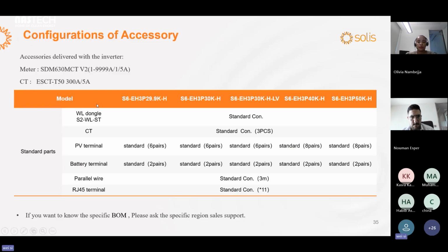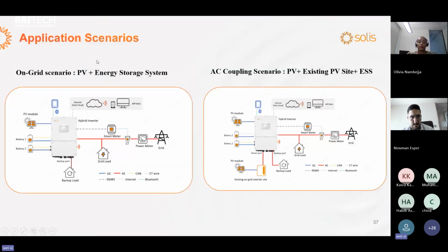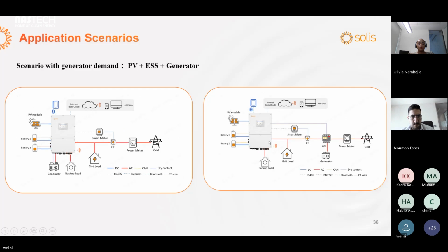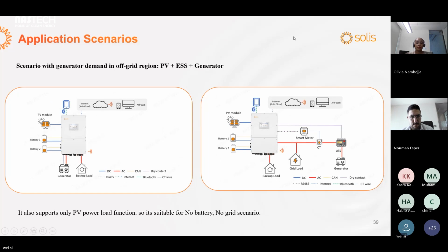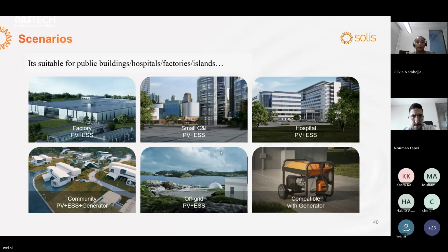About the configuration of the accessories, we provide the dongle, the CT, PV terminal, battery terminal, the parallel wire, and the RJ45 terminal. About the application scenarios, one is very common, the on-grid scenario, with PV and the energy storage system. One is the AC coupling with the generator on the smart port or on the grid side. In the off-grid region, we can also work normally off-grid. So it is suitable for public buildings, hospitals, factories, and islands.